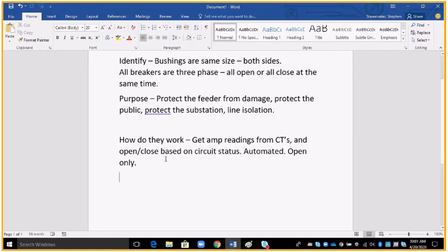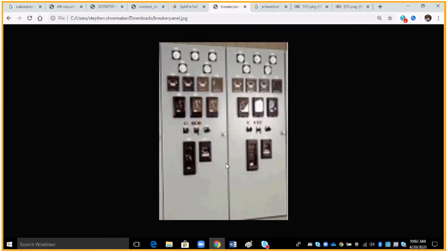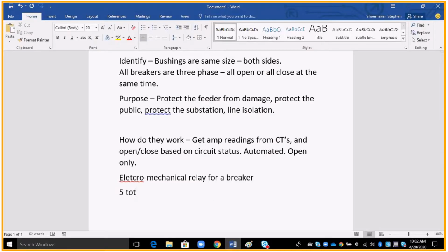All right, so electromechanical relay, breaker. Here we go with the attributes. First, the ones that you need to be concerned with as an entry lineman: how many phases do I have? This is labeled A relay, B relay, C relay, ground relay, and this one right over here to the side is what they call a reclosing relay. So how many relays do I have total for a distribution breaker? 1, 2, 3, 4, and 5. 5 total relays.